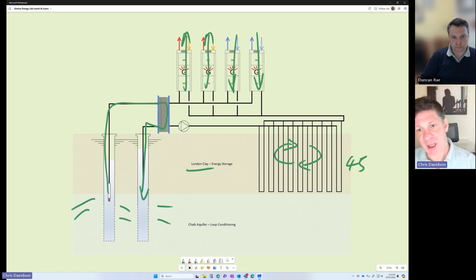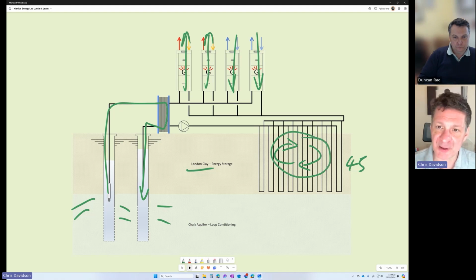And the name of the game here is, unusually, most ground loops are designed and left to operate on their own. What we're actually doing is actively managing the temperature in this ground loop in order to optimize the efficiency of the system by scheduling the loads on and off and utilizing the water wells.